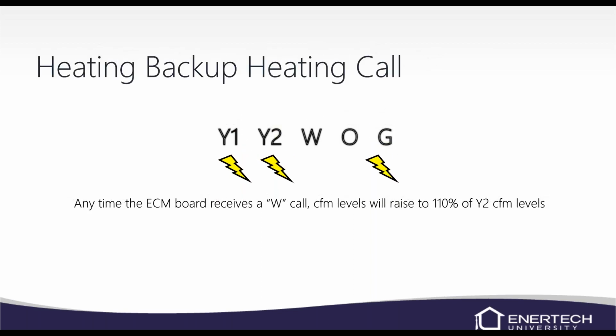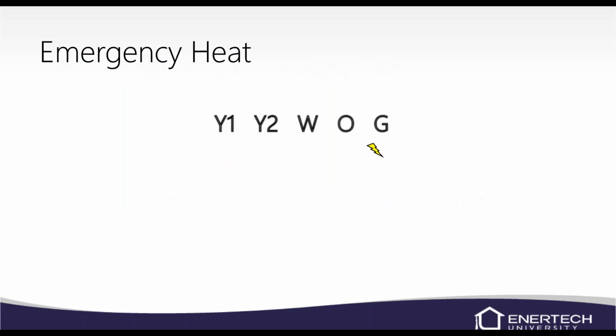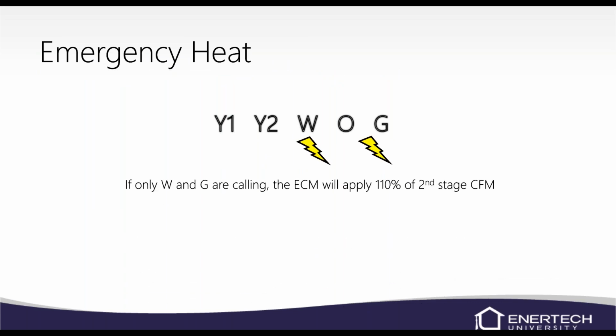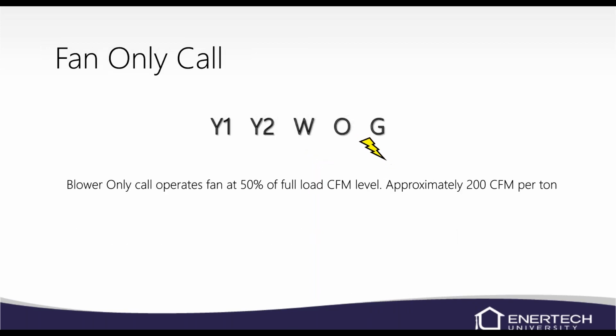When we get a backup heating call, anytime we have a W call, the ECM will ramp up to 110% output to give you a little bit of extra airflow for the electric heaters. Emergency heat call will just be a W call, and again, that's 110% of second stage or Y2 CFM levels. A fan only call would be 50% of Y2. So, if you got 1200 on your Y2, you'd have 600 CFM in your G call.